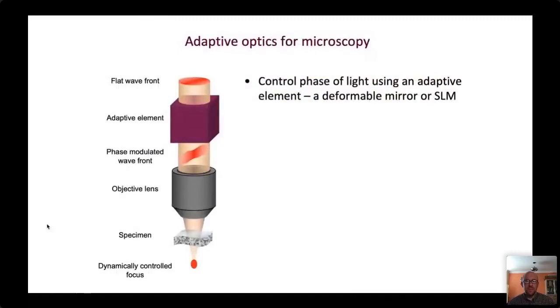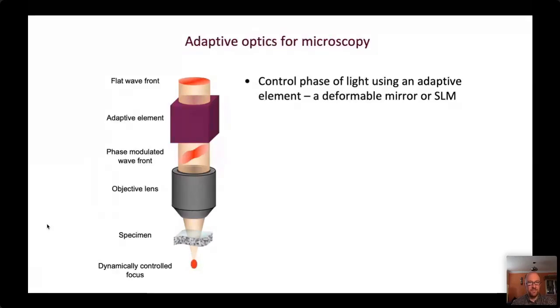The principle of adaptive optics is that we include an adaptive optical element in the microscope to control the phase of the light. Taking a laser scanning microscope as an example, the laser beam is passed through an objective lens and scanned around the focus inside the specimen. The specimen, because it has variations in refractive index, introduces phase aberrations, so we use the adaptive element to pre-modulate the wavefront to cancel out whatever distortion is introduced. A similar argument applies to the imaging path as well.